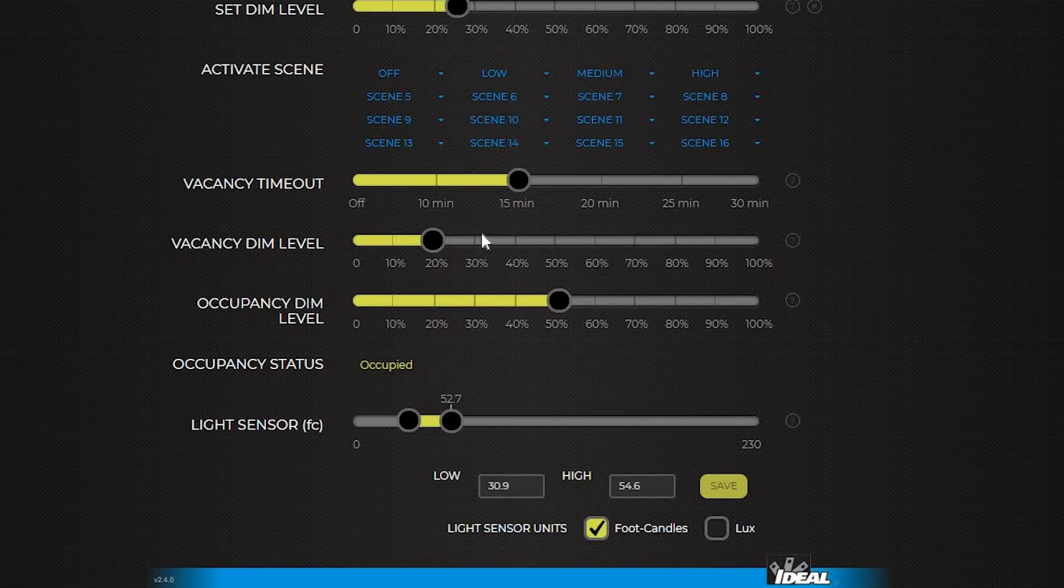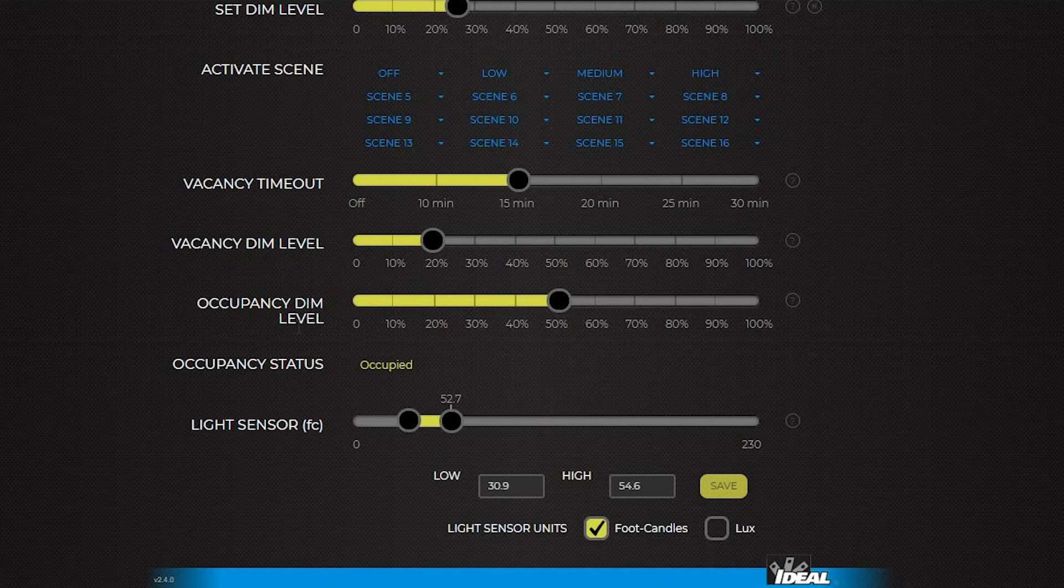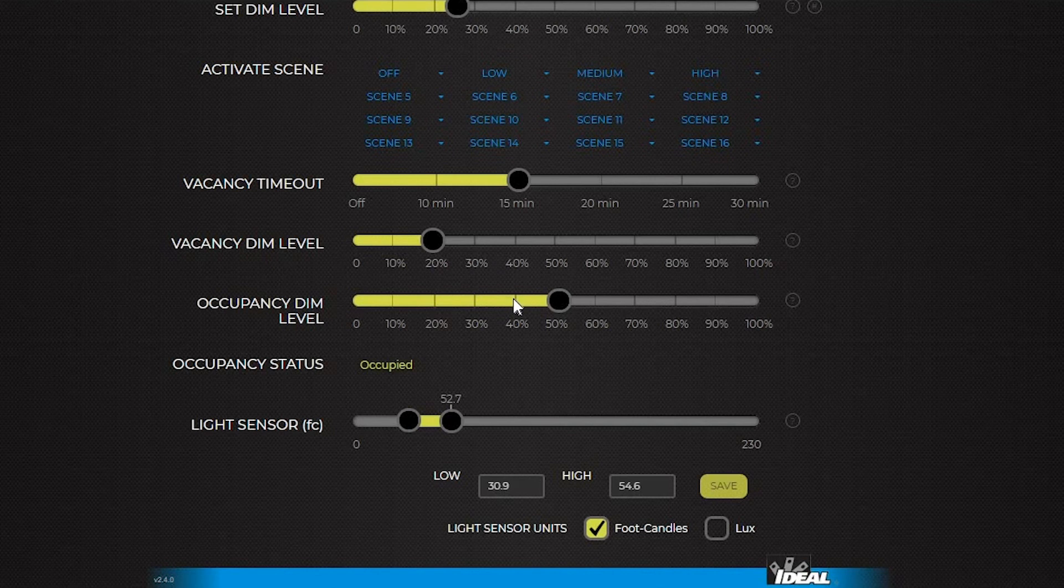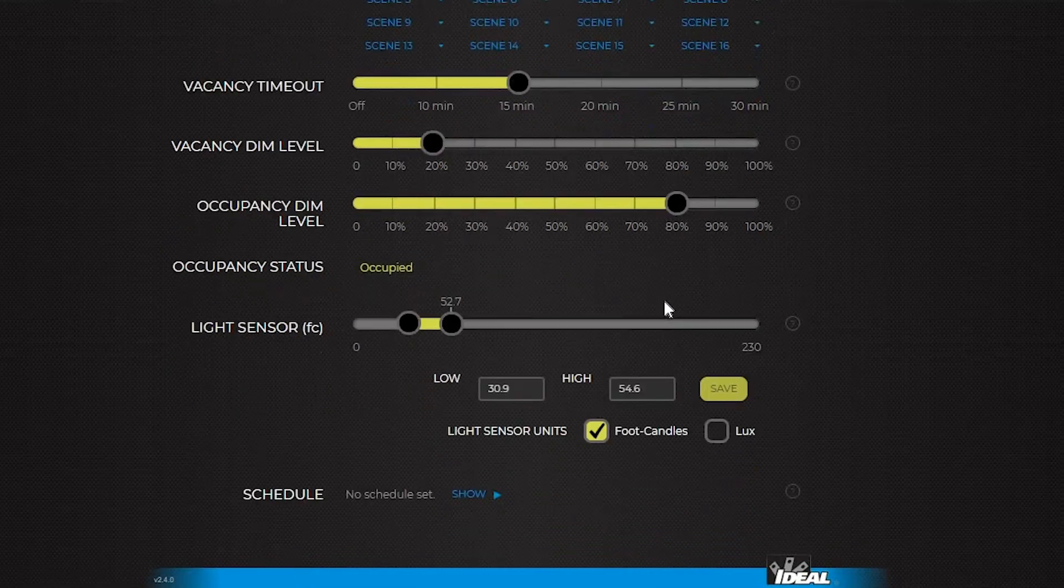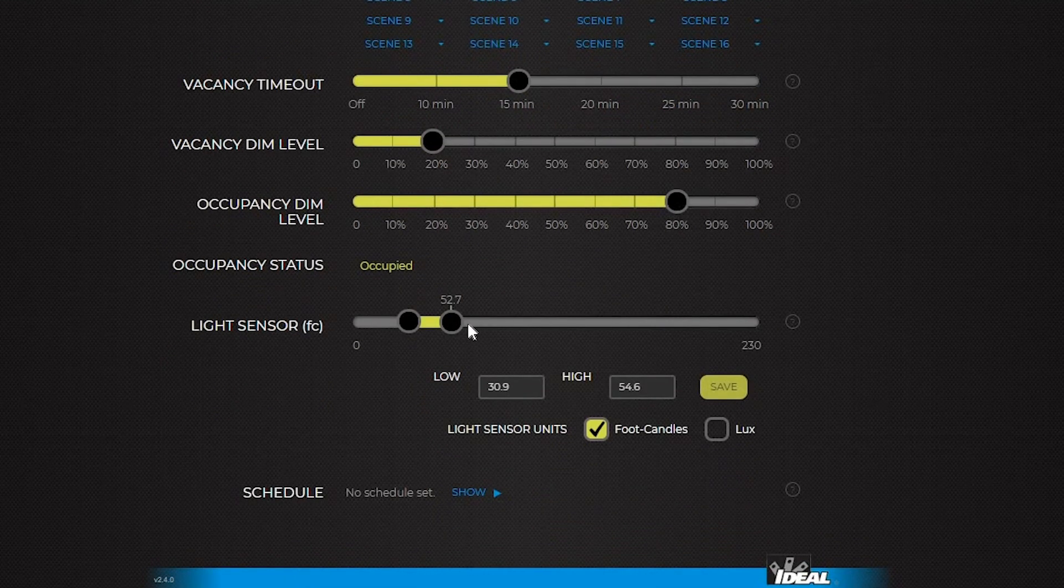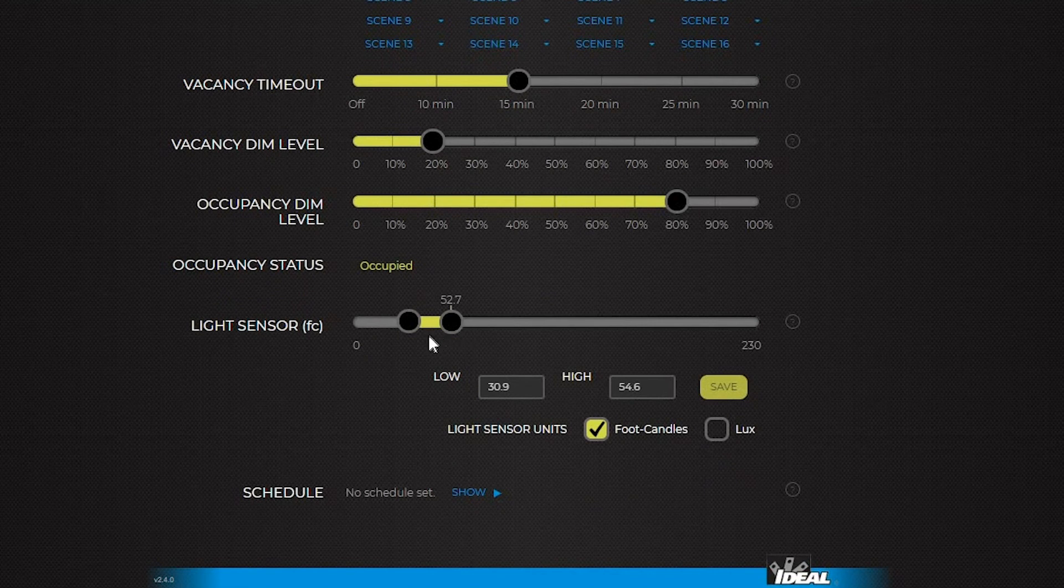The occupancy dim level is similar, but it controls the level the lights go to when the room becomes occupied. If you're in occupancy mode instead of vacancy mode, this is the level that will be used. By default it's set to 50 percent, but you can select any level. The light sensor is where to select low and high set points, as well as to see what the current reading of the light sensor is.